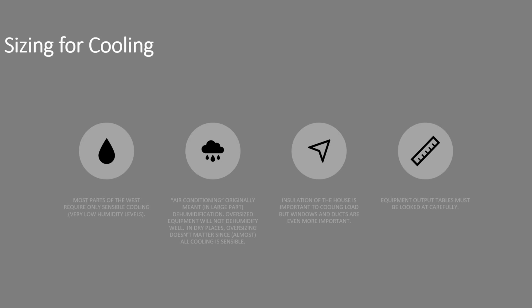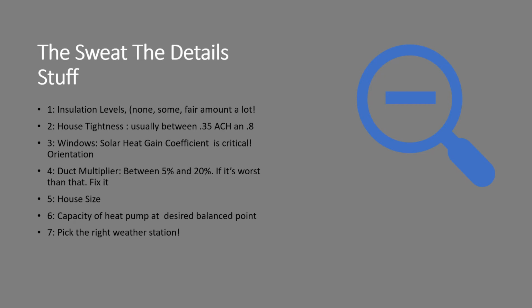Insulation of the house and good windows and good ductwork are probably the biggest factors that are going to influence the size of the heat pump that you put in. And I'm sorry, nobody likes to look at detailed capacity tables, but to pick the right system, especially for cooling, you really have to look at them. In summary, these are the items you sort of have to sweat the details a little bit on. Insulation levels, don't worry if it's an R33 or an R38. Doesn't matter that much, but none, some, or a fair amount sure matters in the ultimate size of the heat pump you put in the house.